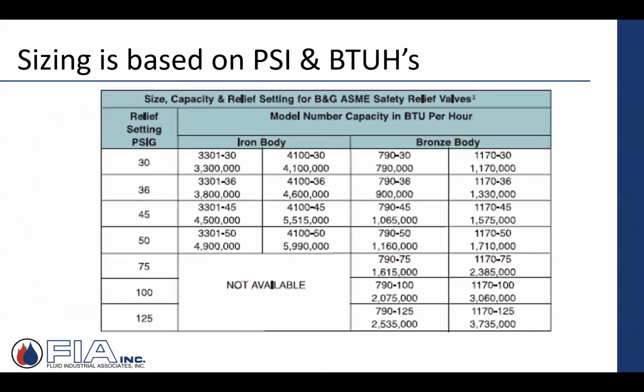So when you look at a spec sheet of a particular pressure relief valve manufacturer, they're going to have a pressure rating on that far left-hand column. So 30, 36, 45, 50, 75, et cetera. But then here, what are the BTUs? What's the capacity in BTUs per hour that the relief valve can relieve? So make sure those two are compatible with the appliance you're specifying or attaching it to.